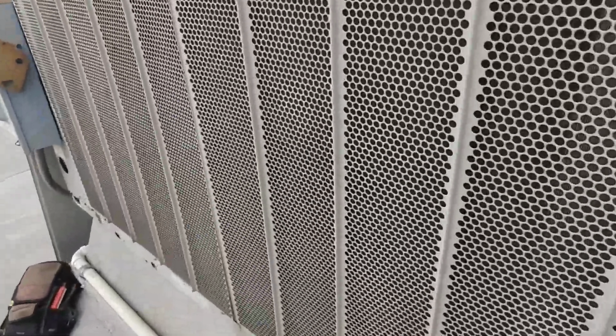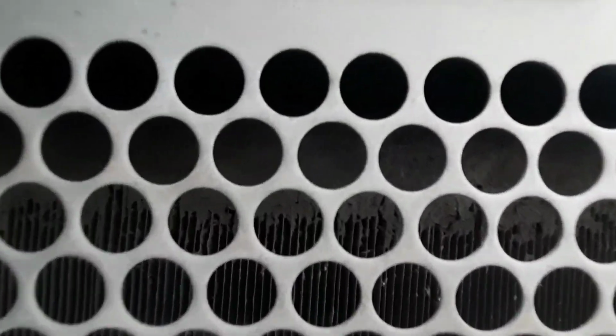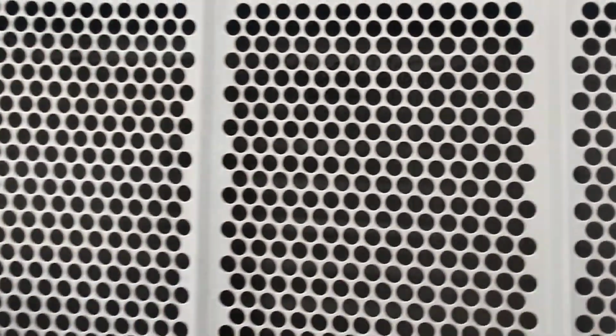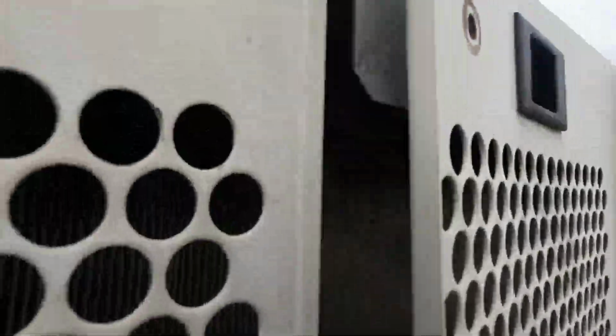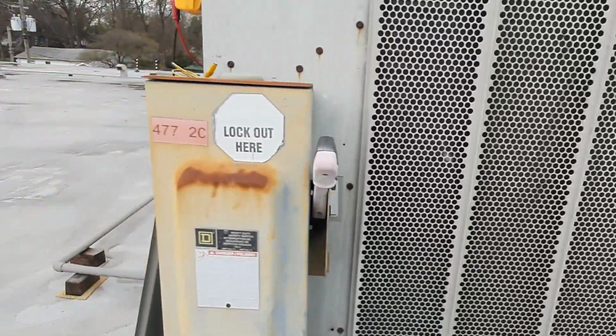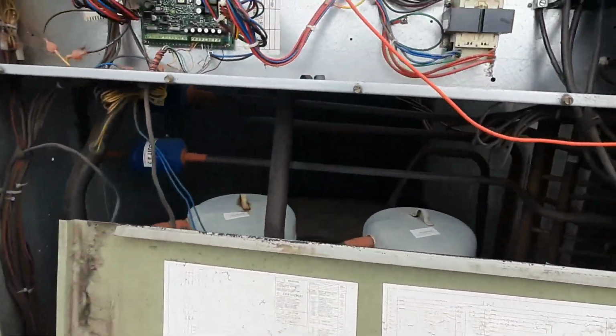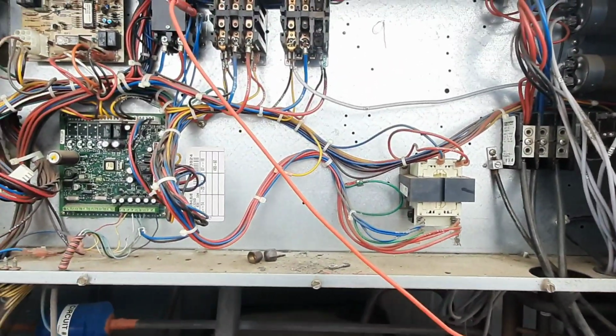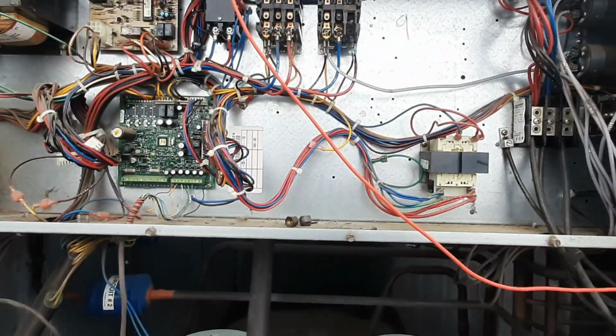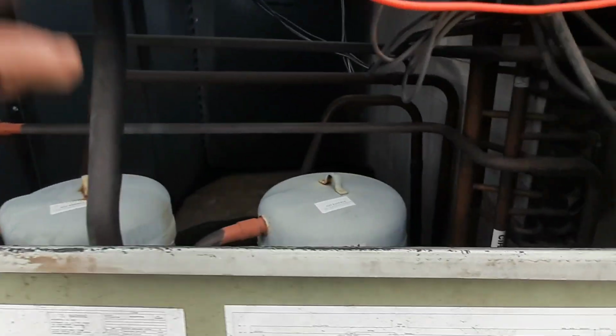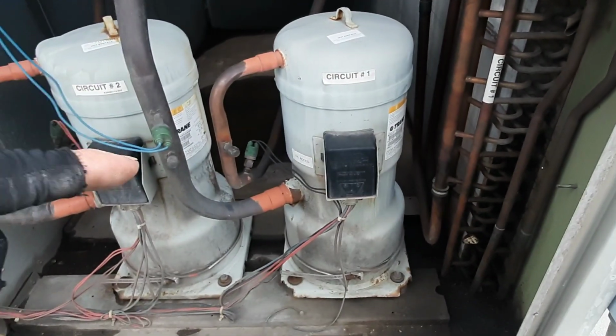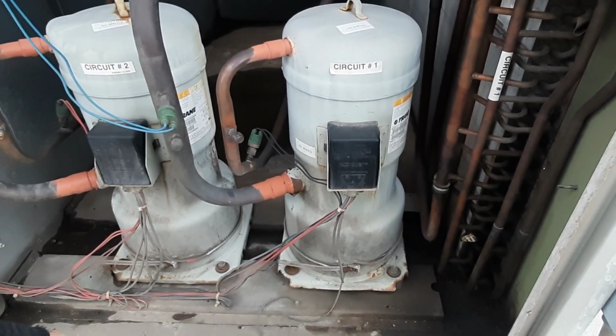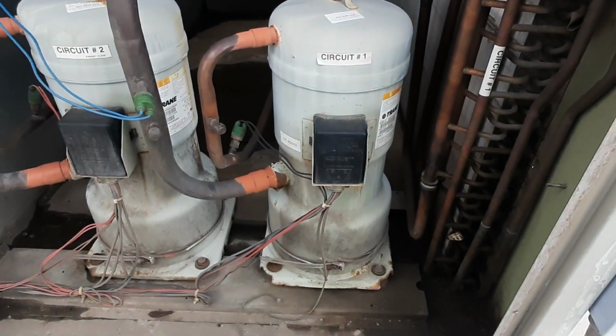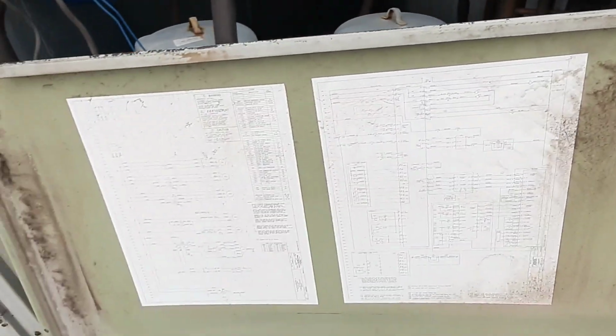Let's get this panel off and look at the heat exchanger. Unless it's been replaced, it's going to be cracked. There is all kinds of crack. Yeah, y'all can't see it on the condenser. That condenser's plugged all to hell. I don't know what the end goal for them here is either, but we've definitely got some problems. So let's look at the heat exchanger and the blower first, and then we can go from there. We'll have to ohm out the compressor and see if it's okay. I don't know how many people have had their hands on this thing over 30 years.